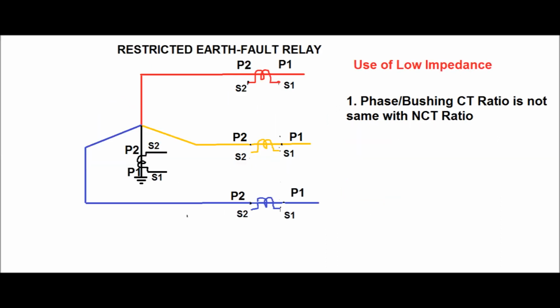Now why should we go for low impedance REF protection? Consider a case where the phase CT or bushing CT ratio is not the same as the NCT ratio, and also the knee point voltage is not the same as that of the NCT. Therefore we must use low impedance REF protection. In that case the relay cost is more, but the external wiring is very simple.